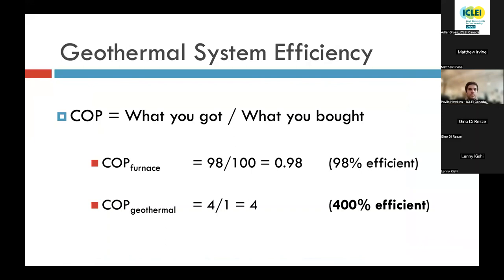So you could rate the furnace with a COP. A COP is simply what you got divided by what you bought. So if you have a 98% high efficiency gas furnace, for every 100 units of energy you're buying, you're getting 98 of them into the house. So that's a 0.98 COP, or 98% efficient. With COP for geothermal, because we're not burning a fuel, we are not limited to 100% efficiency. We're using that heat pump to literally pump heat from outdoors to indoors, and the electricity, or the energy we're buying, which is electricity, is enabling us to collect and distribute more heat than we're purchasing. So we typically would get an efficiency, or a COP, of around 4. Next slide.